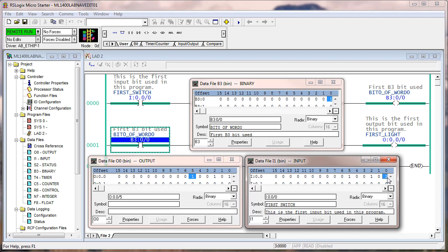The controller's in the program mode. The logic cannot change the state of any bit in the controller's memory, but any external device, like your computer or an HMI, can change it if it has established communications with the controller and has an interface to do it. So in other words, if you're connected up with an HMI or a laptop, you can, from those external devices, move the bits around. If the controller's in the run mode, all the above is true, and the executing program files can change the state of any bits of memory that the commanded instructions are addressing.